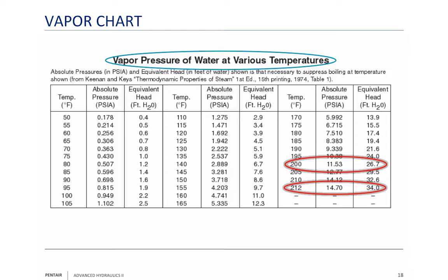The Mile High City means it's 5,280 feet. What we're seeing here is about every 2,000 feet you're going to lose 1 pound of pressure. So at 4,000 feet you lose 2 pounds of pressure. Then at 1,000 feet you lose another half a pound of pressure. And finally, the last 280 feet, we're going to call it 0.2. Why? It makes the math easier. So 2 plus 0.2 plus 0.5 equals 2.7. 2.7 puts us right around 12 psi.